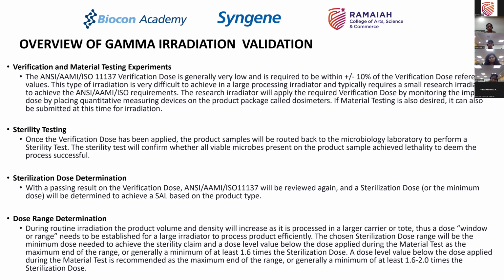The research irradiator will apply the required verification dose by monitoring the imparted dose, by placing quantitative measuring devices called dosimeters on the product package. If the material testing is also desired, it can be submitted at the time of irradiation. So let's understand this a little bit.